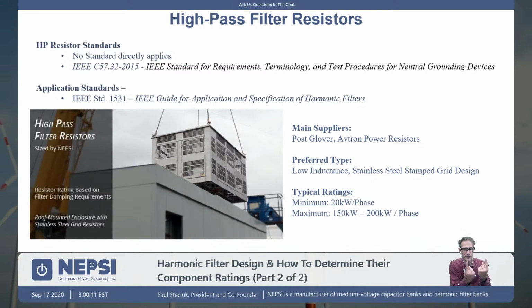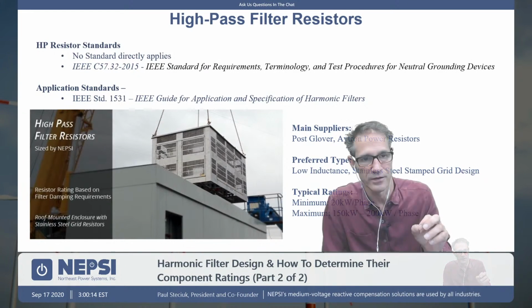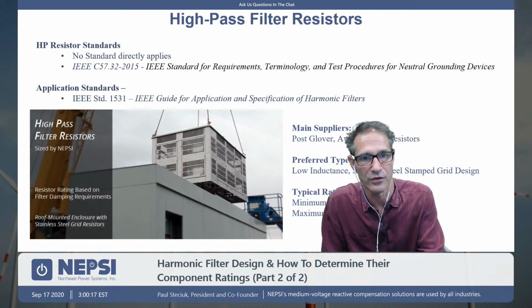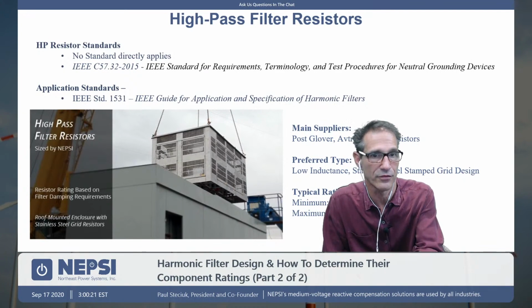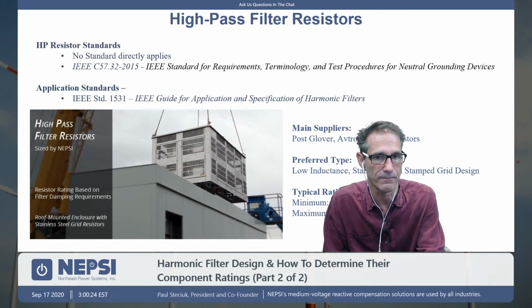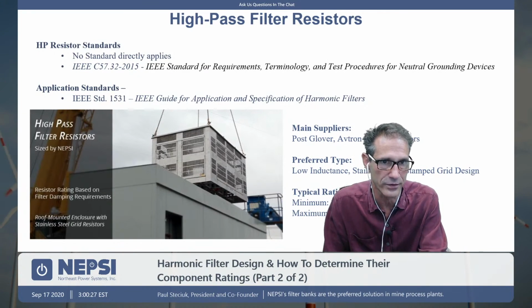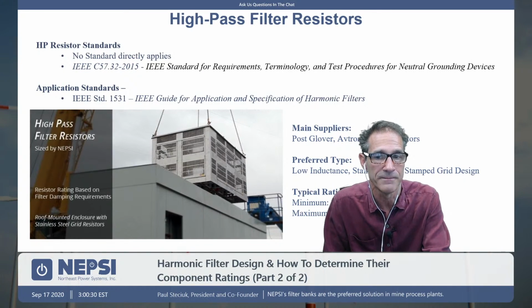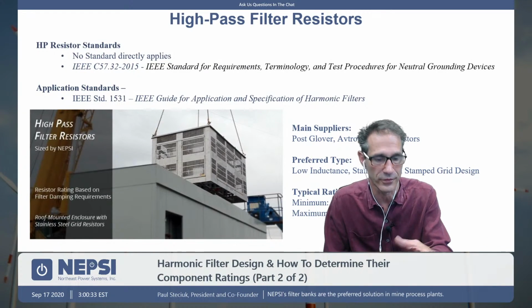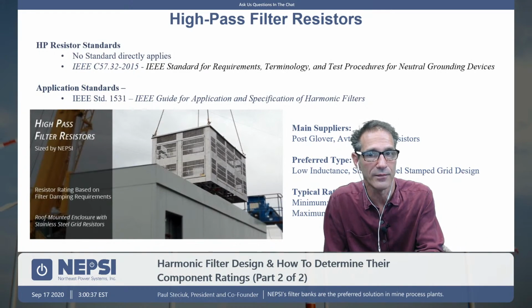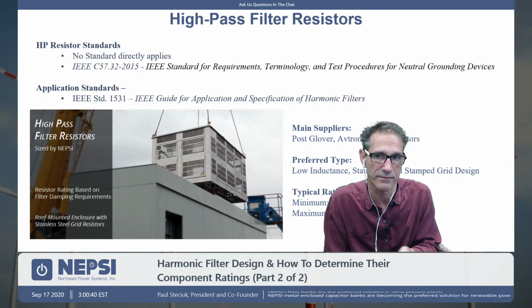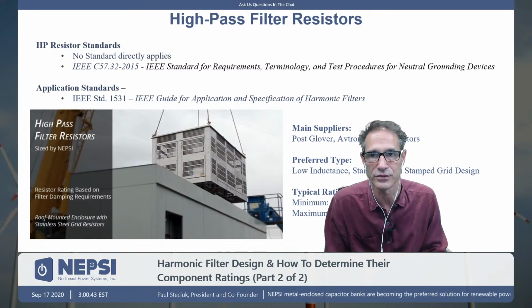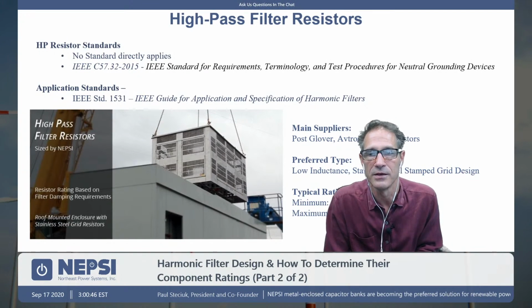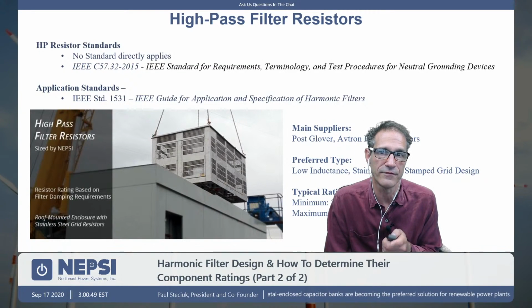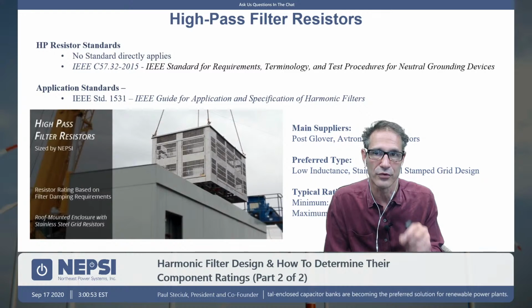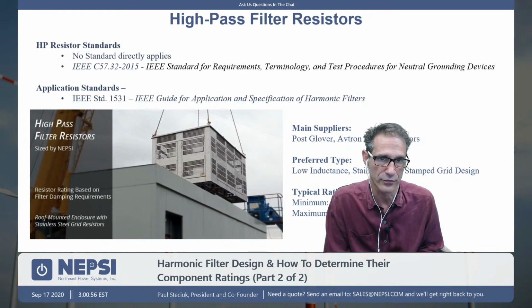We use roof bushings up through the roof. It's important that you specify real roof bushings with both high voltage and ground shields built into that roof bushing. Okay, so if there's a failure point, you don't want to use simple pass-throughs. You don't want to use PVC conduit, anything like that. You don't want to use medium voltage cable through a tube because over time those can fail. So you want to specify a bushing that has both a ground and a high voltage shield built into it, basically a bona fide bushing. There are some standards, IEEE 57.32, but these standards don't directly apply to harmonic filter resistors.